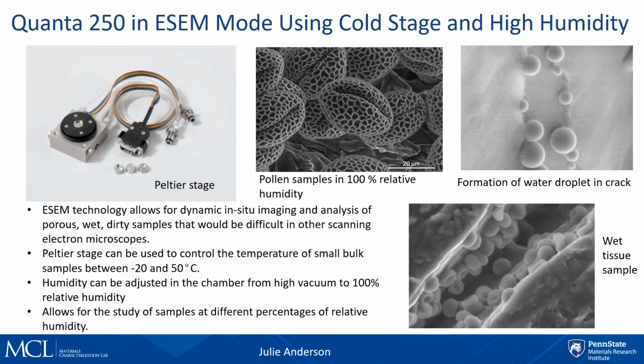So at the MCL, we have a Quanta 250 that has the E-SEM mode using a cold stage and high humidity. The E-SEM technology allows for dynamic in situ imaging. A Peltier stage can be used to control the temperature of a small bulk sample between -20 and 50 C. The humidity can be adjusted in the chamber from high vacuum to 100% relative humidity. It allows for the study of samples at different percentages of relative humidity.